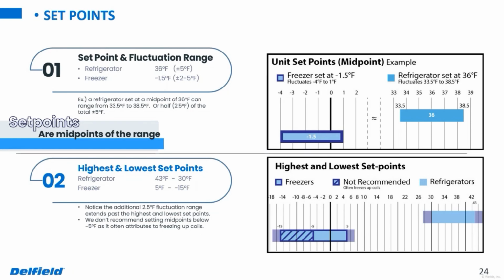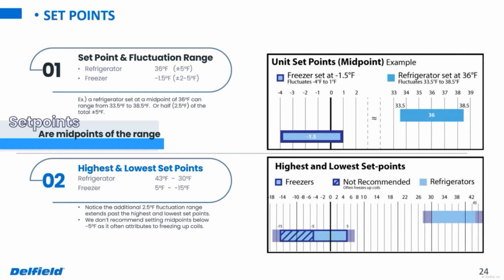But normally these units that we build, like the fry freezers, are going to be on the line next to a fryer. There's going to be a lot of heat in the kitchen where they're located. So setting a control much below that -2 range could give you some issues, potentially with freeze ups and extended compressor runtime. They're turning over product so quickly, and they're in and out of the cabinets quite a bit as well. So again, if you're giving me and Bud a call, we're going to tell you that 0 to -2 degrees, somewhere in that area, for a freezer is going to be a pretty good spot for a set point.